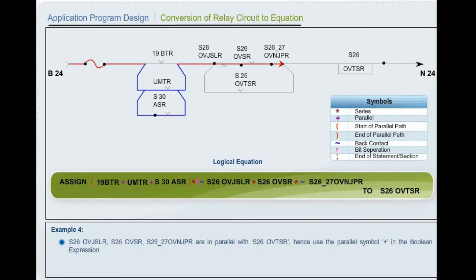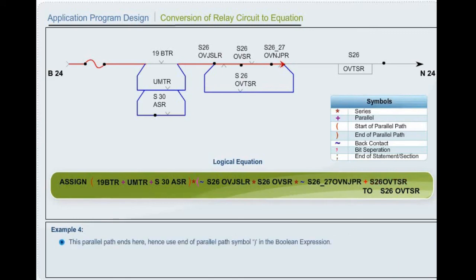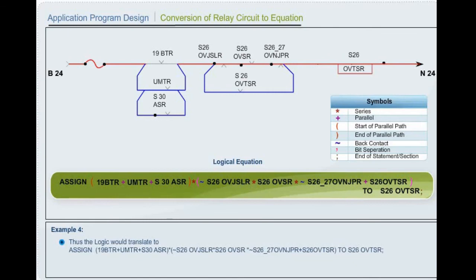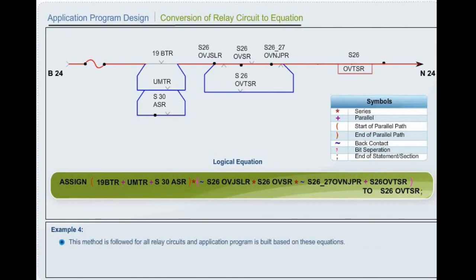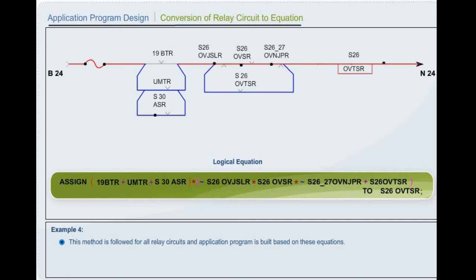S26 OVJ SLR, S26 OVSR, S26 underscore 27 OVNJPR are in parallel with S26 OVT SR. Hence, use the parallel symbol in the Boolean expression. This parallel path ends here. Hence, use end of parallel path symbol in the Boolean expression. This logic is required to activate the vital output S26 OVT SR. Terminate the Boolean expression with the end of statement symbol. Thus, the above circuit would translate to the Boolean expression. This method is followed for all relay circuits. An application program is built based on these equations.